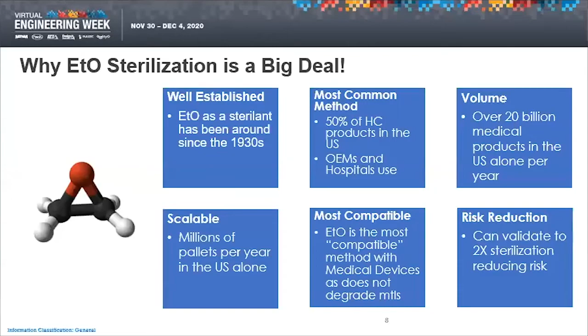Finally, another consideration lending itself to EO is the product can be validated to run through multiple EO cycles. This is an important risk reduction measure to single shot sterilization, in that if there's a problem with the run, 100 steps, 20 hours, what could go wrong, or there's an equipment failure, say you lose a vacuum pump, you can validate it to run through a second cycle and not scrap the product. Some of these other technologies are single shot, and if you've got expensive product, particularly combination products with a drug constituent, there's risk that something could go wrong and you could lose the load.